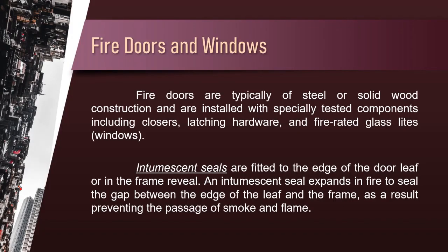Fire doors and windows. Fire doors are typically of steel or solid wood construction and are installed with specially tested components including closers, latching hardware, and fire-rated glass lights, or windows. Intumescent seals are fitted to the edge of the door leaf or in the frame reveal. An intumescent seal expands in fire to seal the gap between the edge of the leaf and the frame, as a result preventing the passage of smoke and flame.